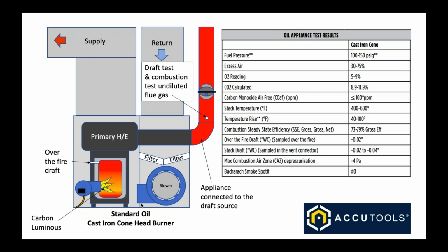It transfers about 6 times more heat energy by radiation than a blue flame does. Just like if you lit off your oxyacetylene torch and you light that acetylene, that bright yellow flame, how much heat it puts off. And then when you put on the oxygen, you know the flame's hotter. It's a way hotter flame, but you don't feel the heat energy as much. And that's because the color of the flame determines how it's going to transfer its energy. Now we're in a larger combustion chamber, so we need more heat energy by radiation.